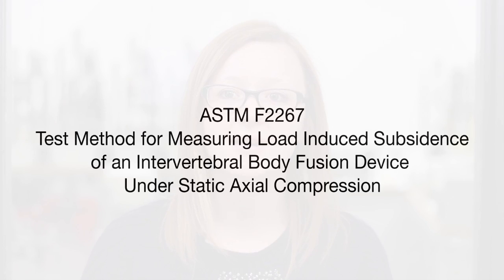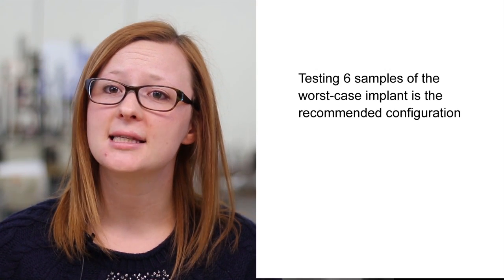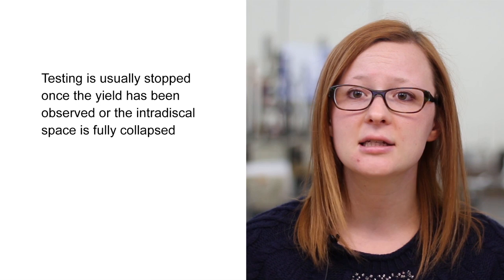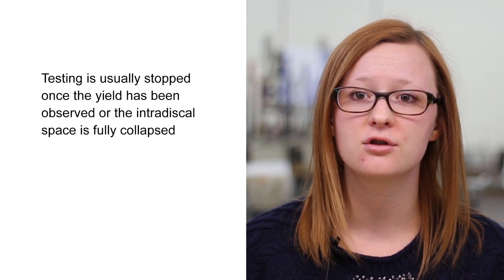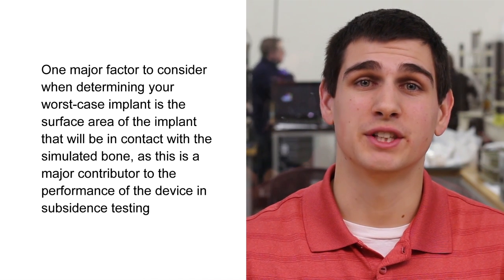The second standard in today's video, ASTM F2267, is a standard test method for measuring load-induced subsidence of an intervertebral body fusion device under static axial compression. The standard allows for comparative evaluation of different intervertebral body fusion devices, providing a basis for mechanical comparison amongst past, present, and future non-biologic intervertebral body fusion devices. Testing six samples of the worst case implant is the recommended configuration, and testing is usually stopped once yield has been observed or the intradiscal space is fully collapsed. One major factor to consider when determining a worst case device is the surface area of the implant in contact with the bone surface, as this is a major contributor in performance during subsidence testing.